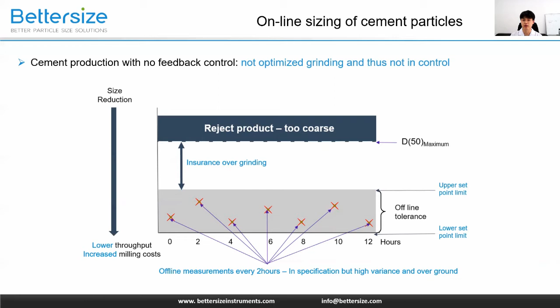The key advantage of an online fineness analysis is not just the capability to make the measurements every minute, but also to optimize the separator speed based on those online measurements. A benefit of that is to create a just-in-specification product all the time with a much tighter tolerance by closing the loop.